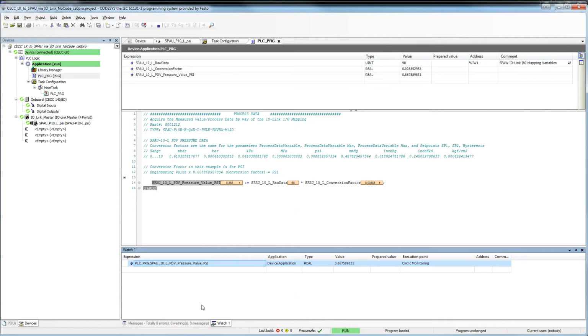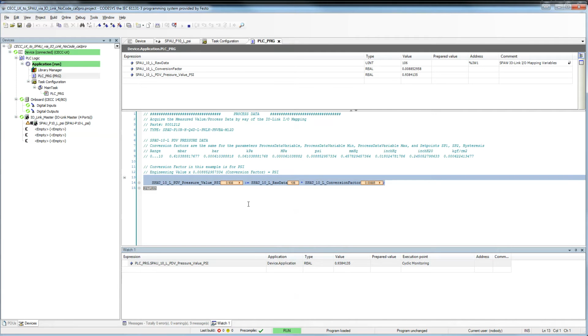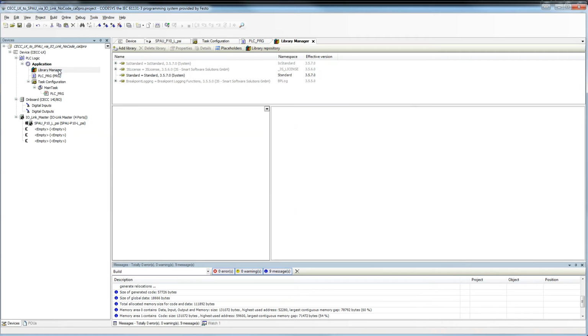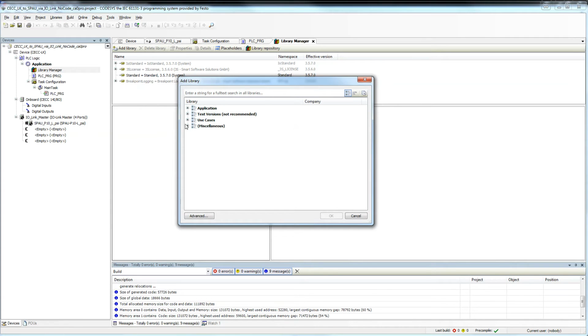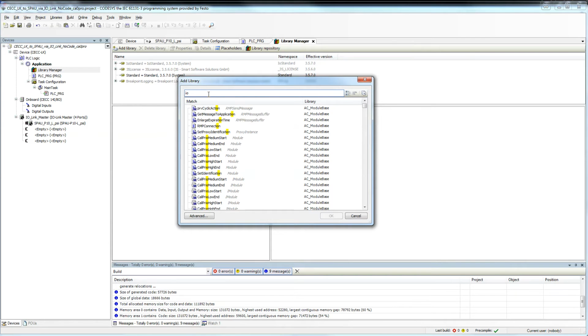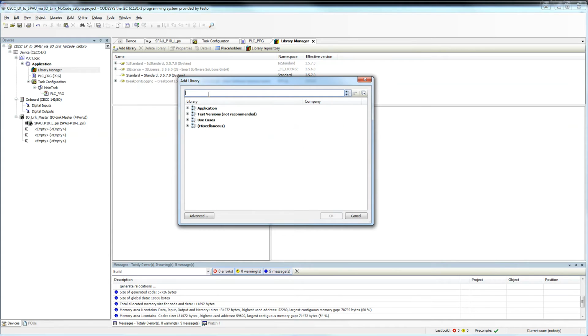If you want to make one more simple thing, typically you don't want to look at the data unless you know that the switch is connected. So if I was to physically connect or disconnect the switch, you'll see, hey, I've got the yellow or orange triangle, but yet because I had no fault reaction or anything like that in the code, I get the last value, which was 0.938. So what you do there is there is a library, IO-Link. Actually, Festo.